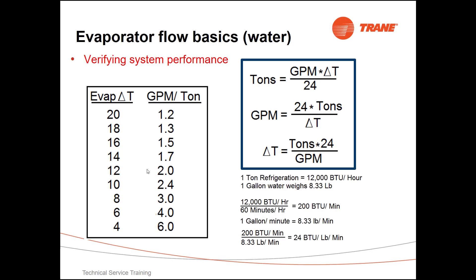So an example would be: let's say we have a machine that's running at 2.4 gallons per minute per ton. That machine should be doing, when it's fully loaded, a 10 degree evaporator delta T — the difference between entering and leaving.